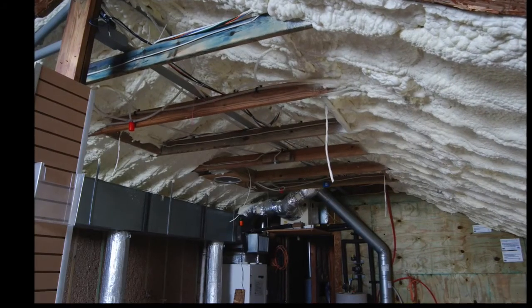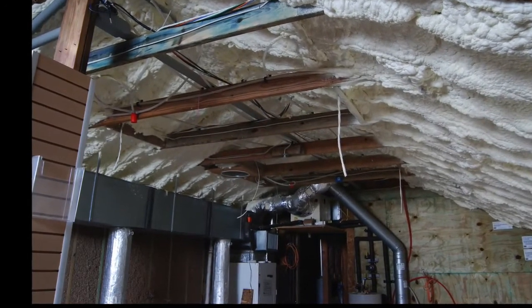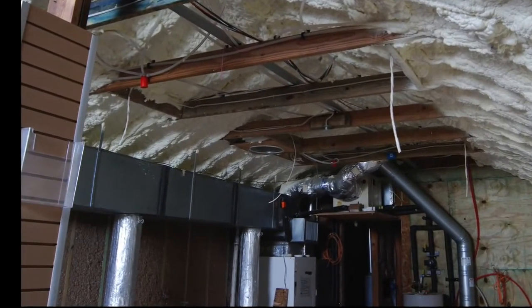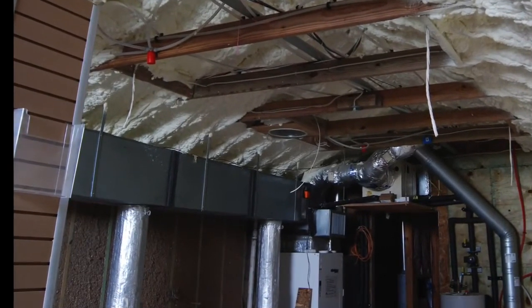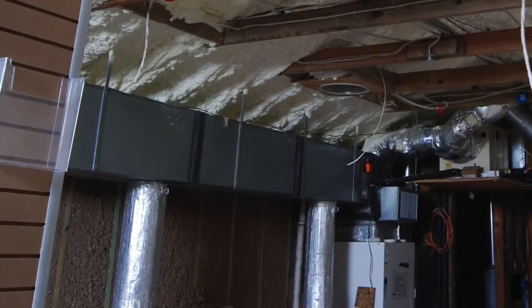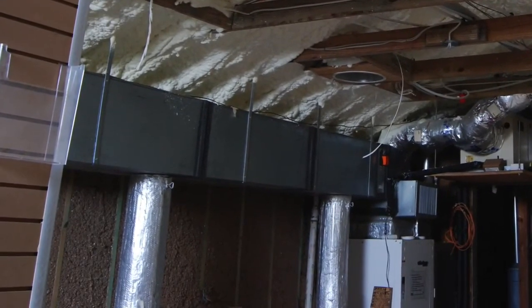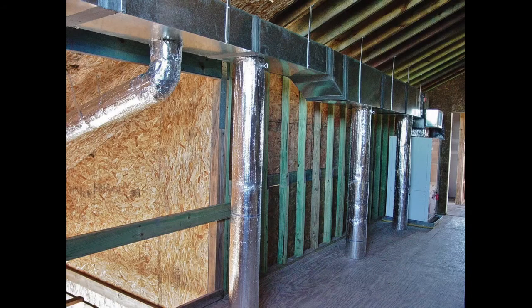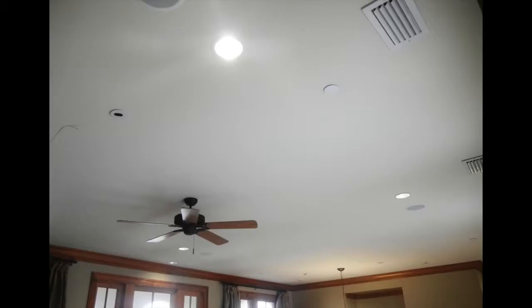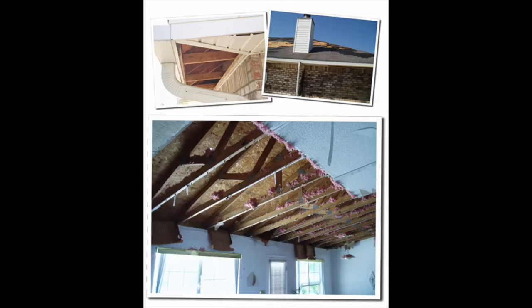Moving the insulation boundary from the ceiling to the roof line puts the air conditioner and the ductwork within conditioned space, eliminating the typically large energy losses from leaky, poorly insulated ducts in hot attics. This reduces the cooling load, so you save money by buying smaller equipment and by saving energy every day. The room ceiling below does not need to be made airtight, saving labor. And no soffit and roof vents omit the risk of wind-driven water intrusion in storms.